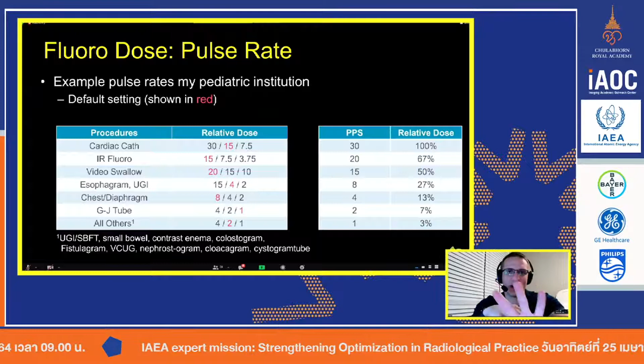And if you have a Philips unit, they're called fluoro flavors, as an example. Siemens has different names, they're all just labeled something different. But in my case, we have 3 dose values, and the red values are the default values. So in the GJ tube, it's defaulted at 1 pulse per second.